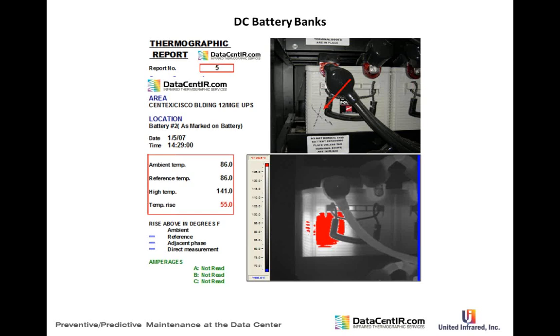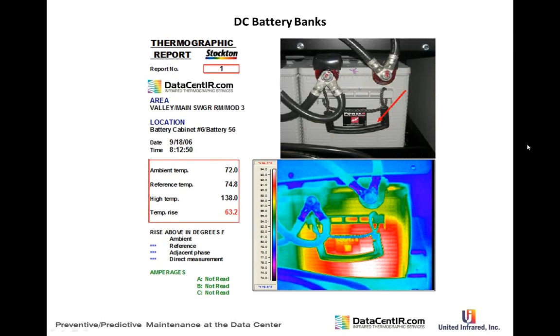Cabinet battery banks — smaller banks — can show internal battery problems. Several failed batteries were found. You must check 2 to 3 minutes, then 5 minutes, then 10 minutes after the battery discharge, because internal problems appear 5 to 10 minutes after the test completes. Another internal battery problem was clearly obvious, noted approximately 15 minutes after the test was completed.